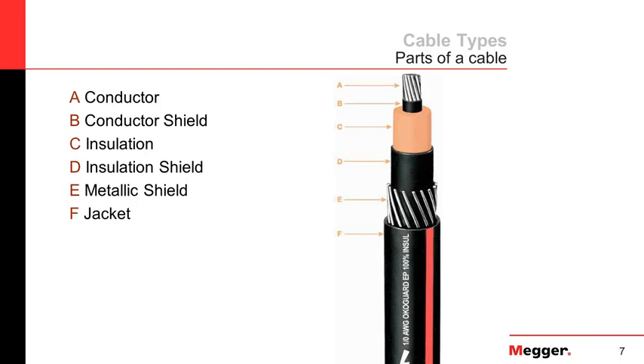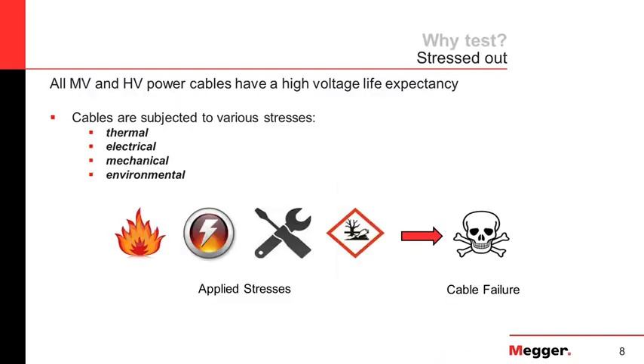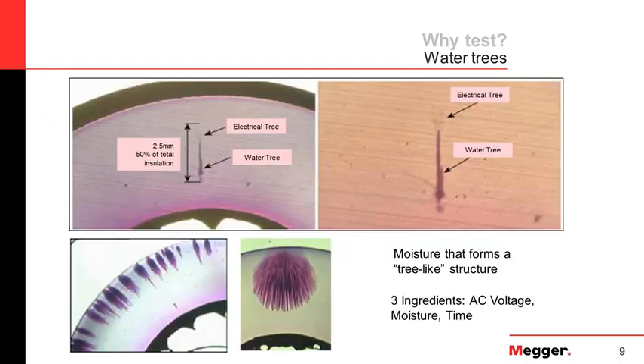Why are we testing cables? Throughout the cable's life, they're subjected to various types of stresses: thermal stresses from short-circuit currents, electrical stresses from transients, mechanical stresses from tight bending radius, and environmental issues like high-moisture areas. All these stresses age and degrade the cable over time, which leads to cable failures. One of the leading aging conditions of medium-voltage cables is something called a water tree — moisture trapped inside the cable that forms a tree-like or bush-like structure. All you need are three ingredients: AC voltage, moisture, and time.